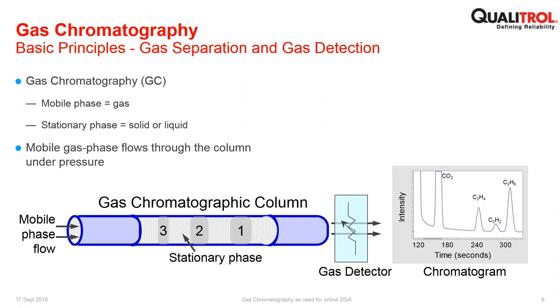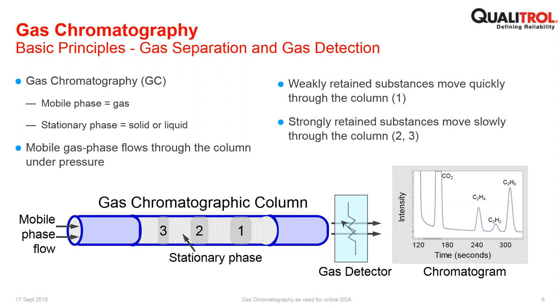The basic principles of how separation, and therefore quantification and qualification, of your dissolved gas sample is achieved. There is a mobile phase. In our case, it's helium, and there is a stationary phase, and this is a solid material which the column is packed with. It can be a number of different compounds, and they're usually proprietary, or specific for the application. But if you were to see it, it's a powder type material. Essentially, as the mobile gas phase flows through the column, it will push anything that is in the column that can move down through the column. So weakly retained substances move quickly through the column and come to the detector first, and strongly retained substances move more slowly and will come to the detector later on.